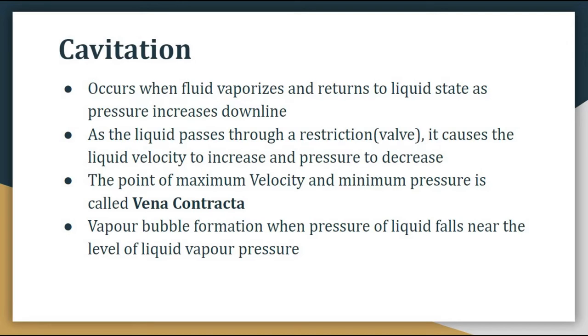Whenever a liquid passes through a restriction, its velocity increases, and with increasing velocity, pressure decreases. The point of maximum velocity and minimum pressure is called the vena contracta — it is the point beyond which velocity cannot increase further or pressure decrease further. Maximum velocity and minimum pressure occur at the vena contracta.